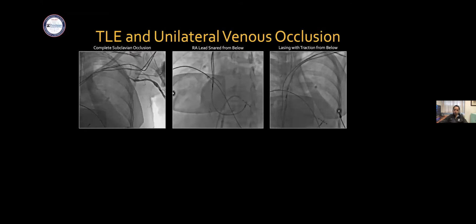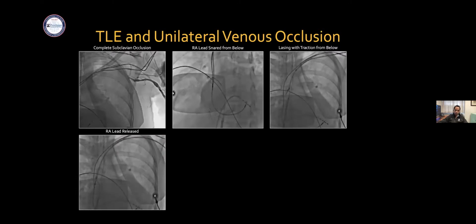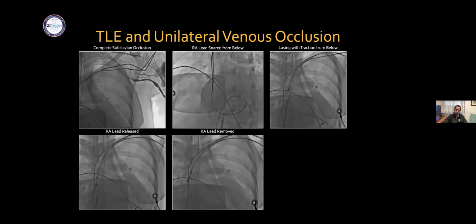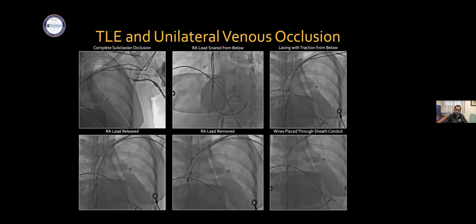Okay. So in this way, we're able to pass the occlusion, eventually remove the snare from the lead, remove the lead from the sheath, and we can use the sheath as a conduit to drop wires. And this is a very common indication for us here at Penn. About 20% of our lead extraction procedures are for unilateral occlusions.